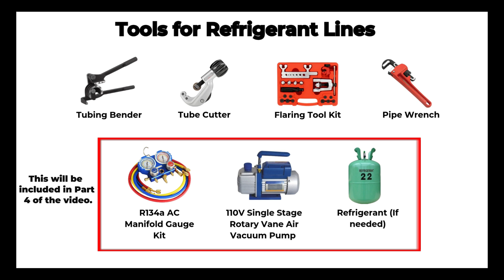Now, for the tools needed for the refrigerant lines, it will require a tubing bender, tube cutter, flaring toolkit, and a pipe wrench. The R134A manifold gauge kit and 110V single-stage rotary vane air vacuum pump will be covered in Part 4. In Part 4, I want to show you how to use these tools and explain their crucial role in system maintenance. The important part is that they remove air and moisture from your AC unit, ensuring it works properly.